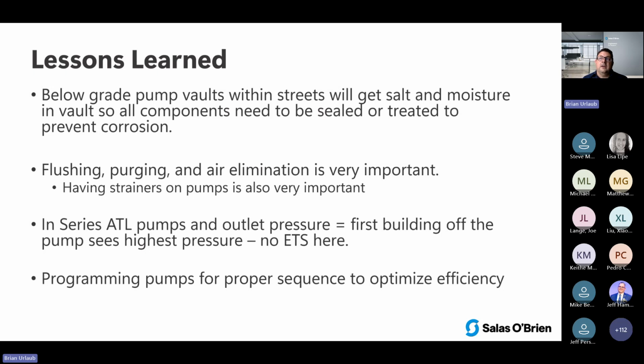Making sure you understand how to get the air out of the system and all the dirt and everything that goes in. This particular project did not go well from a flushing perspective. They tried to use a hydrant. A hydrant couldn't push 2 miles of 6-inch pipe. So there was a lot of air in the system. There was a lot of stuff still in the systems. They ended up having impacted impellers on the pumps right away. So they had to pull the pumps and clean them and change impellers. So just making sure the systems get flushed and purged is so critical, in understanding how to do that. Because these are large systems, large volume. They take big pumps in order to get the air out and get the debris out.